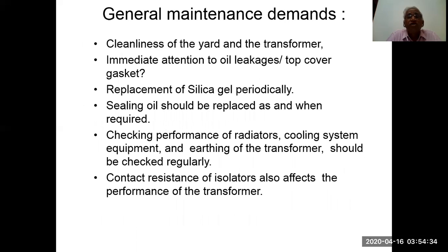General maintenance demands cleanliness of the yard and the transformers, immediate attention to oil leakages at top cover gasket, replacement of silica gel periodically, sealing oil should be replaced as and when required, checking performance of radiators, cooling system, equipment and earthing of the transformer should be checked regularly. Contact resistance of isolators affects the performance of the transformer.